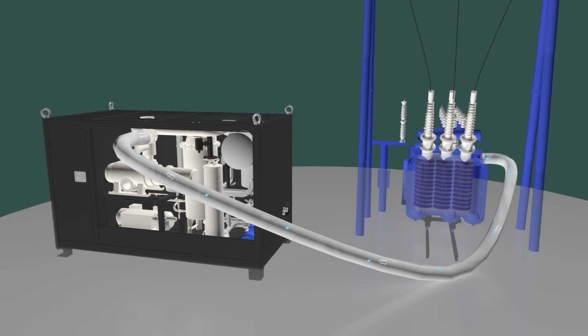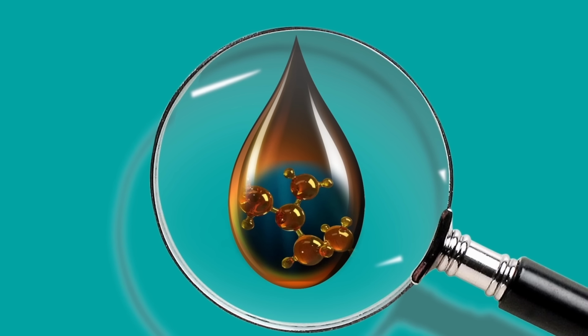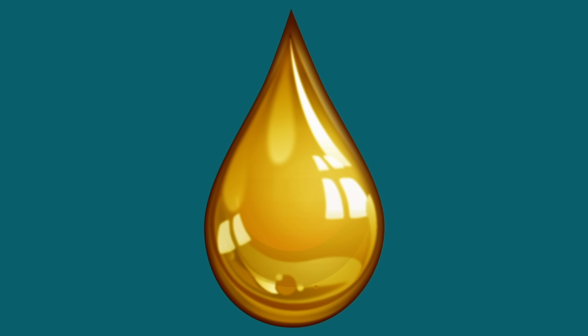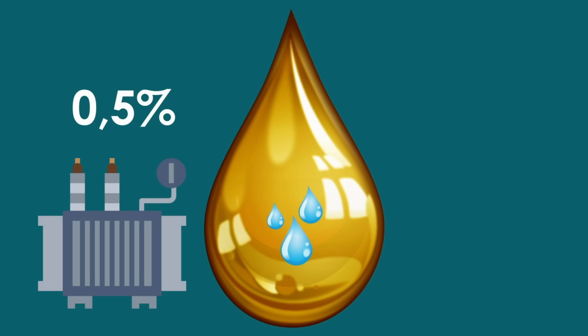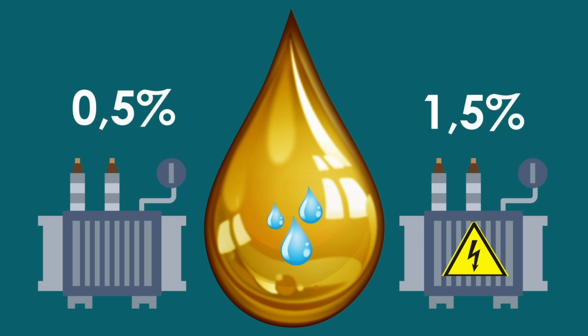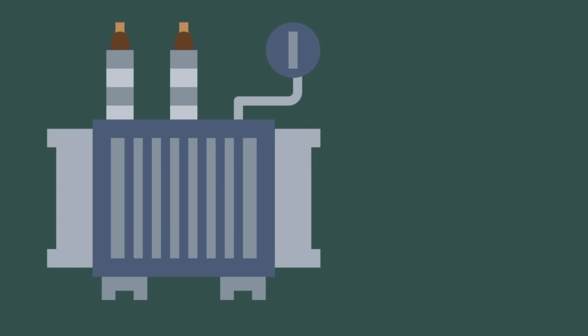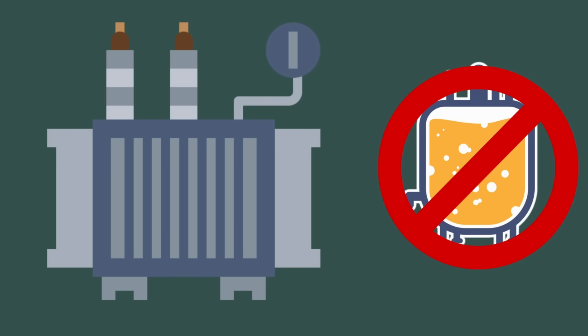This cycle, heating with hot oil and vacuuming, is repeated several times until the moisture content of the solid insulation is not more than 0.5% by mass for new transformers and not more than 1.5% by mass for transformers in operation. The tanks of some older transformers may not withstand a full vacuum.